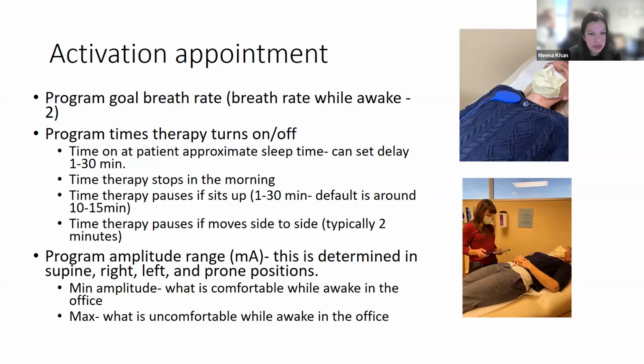The other thing we program is the amplitude, which is in milliamps. So we determine the range of this, and you determine this for different sleeping positions. So you have a different range for supine, right, left, and prone positions, because their need for treating their sleep disordered breathing may be different from position to position. How you start out is that the minimum amplitude of this range is what's comfortable for them while they're awake in the office. And again, you test this in all 4 positions. And then the max is what's uncomfortable while they're awake in the office. And that's how you set the range.